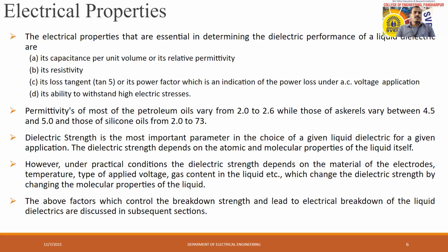It should have, firstly, capacitance per volume, meaning its relative permittivity, epsilon. Then its resistivity, rho. Its loss tangent, tan delta, or power factor, which indicates the power loss under AC voltage applications. And it should have the ability to withstand high electric stresses. So these are all the electrical properties of these oils or dielectric liquids.